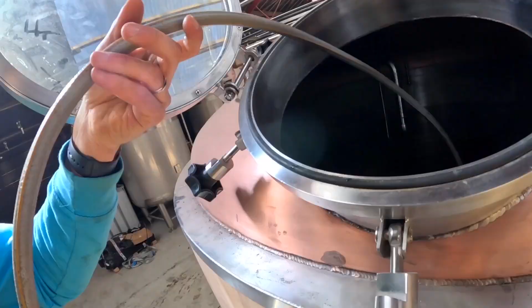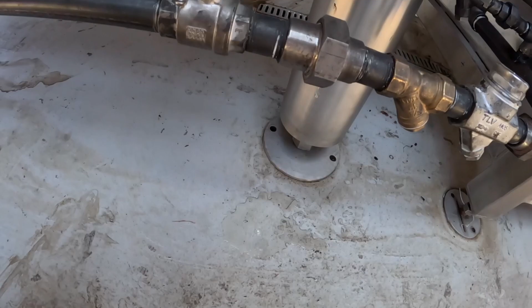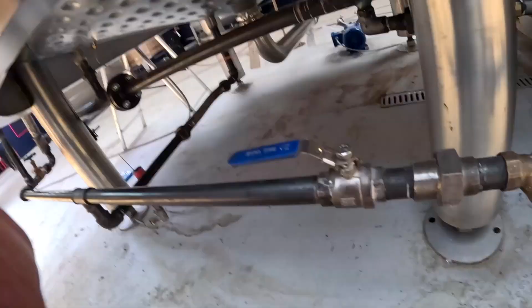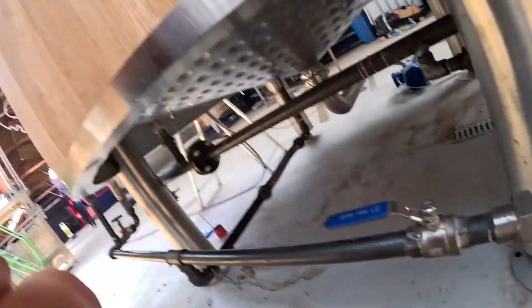So in fact, if I climb up this ladder, we've been filling the wash still with water so that we've got something to test. We can heat up the water as our test run. Ooh, looks murky. That's hot. Yeah, that's already hot. The steam in there is over 100 degrees, and we're just looking for things like this. Yeah, we've got another leak. But that's it, when the pipes expand, you're going to get moments where it's going to leak a little bit like this. And it's expanding as it heats up, of course.